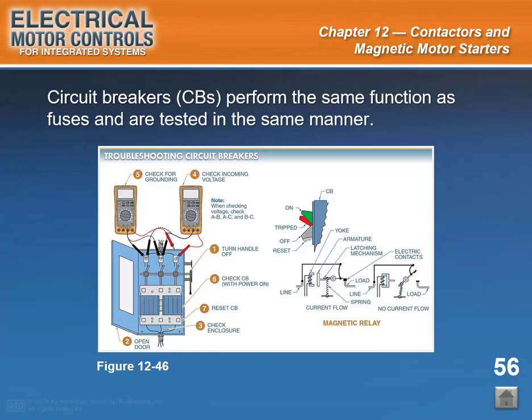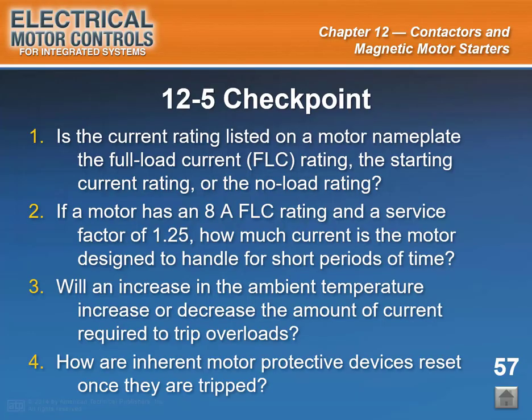CBs are magnetically operated and are reset after an overload. A DMM set to measure voltage is used to test CBs. CBs perform the same function as fuses and are tested the same way. See complete procedural list on page 264. End of slide 56. Start of slide 57.